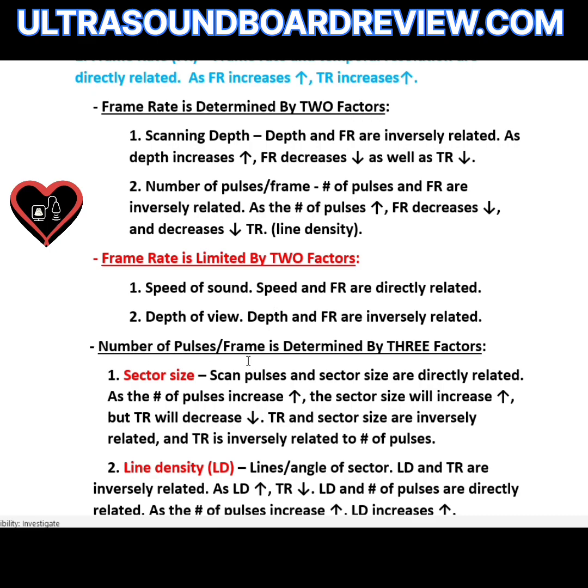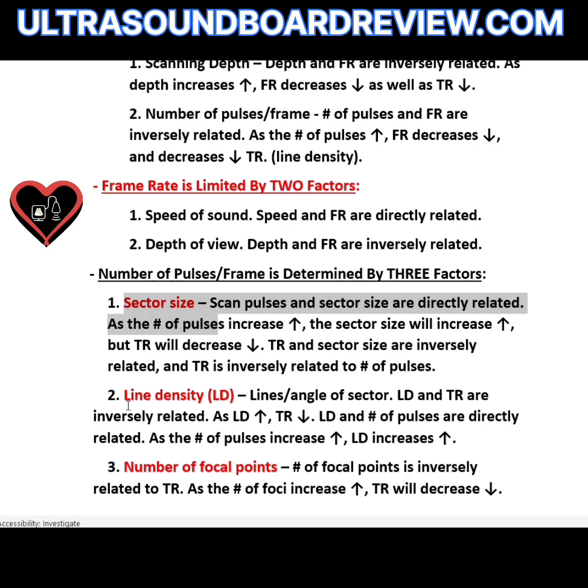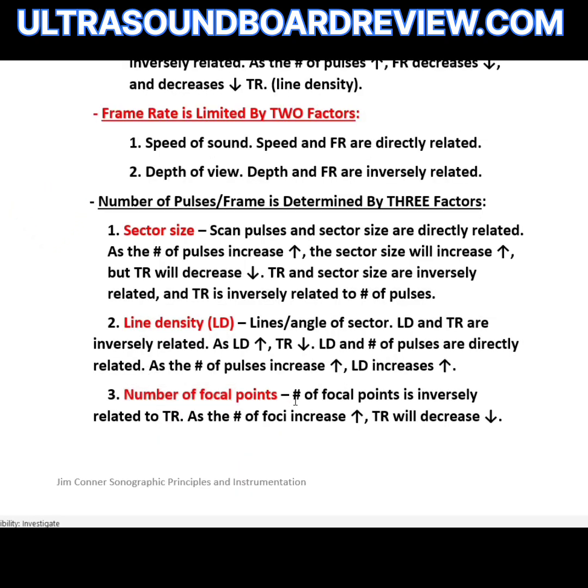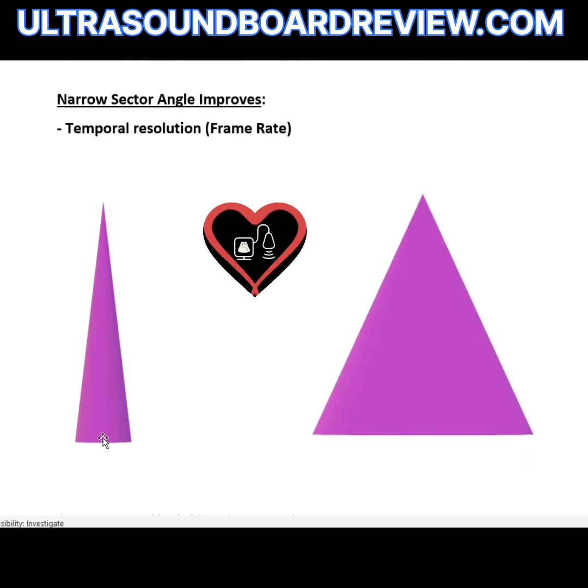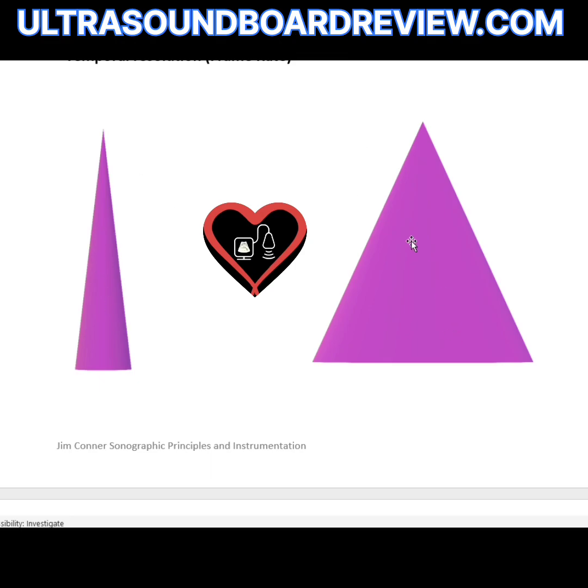The number of pulses per frame is determined by three factors: sector size, line density, and the number of focal points. Regarding sector width, a narrow sector width has the best temporal resolution and frame rate because there are fewer lines per frame and fewer pulses. When you widen your sector width, you have more lines and more pulses per frame, which degrades temporal resolution and frame rate.